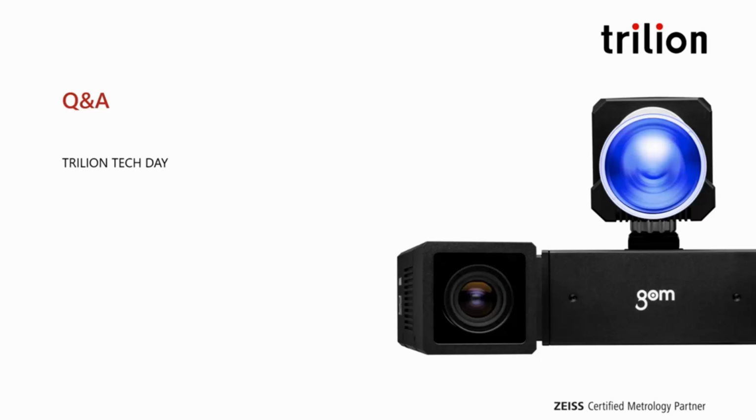Cool. I think that's it. Any questions from the room? Yes. Repeat that question. Yeah, so we have somebody in the room that asked whether the kiosk mode is implemented through scripting or how we actually go about implementing kiosk mode. Yeah, and absolutely. It's through Python scripting, as well as templates created through the Zeiss Inspect ecosystem, but mostly the Python scripting.